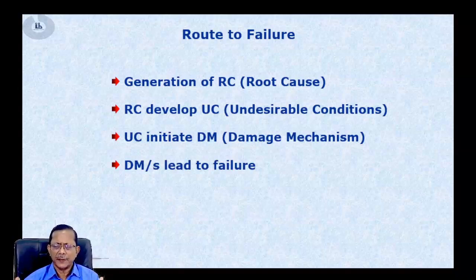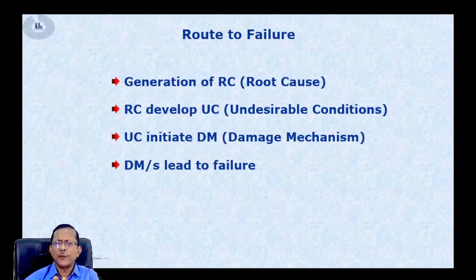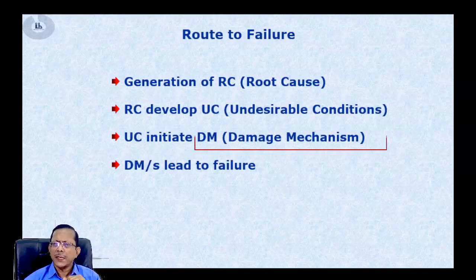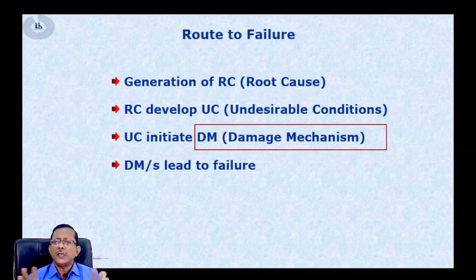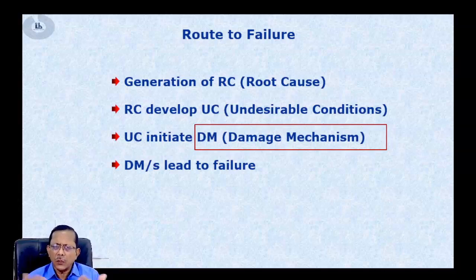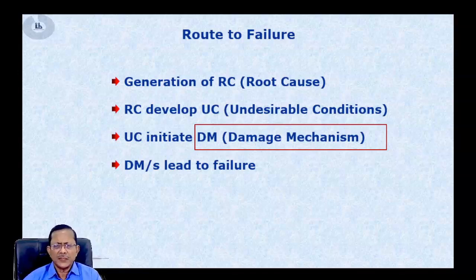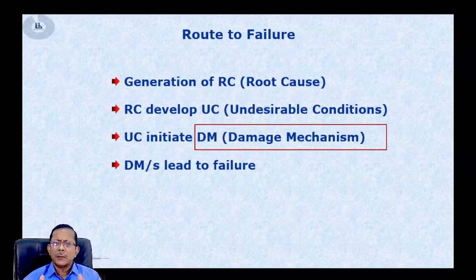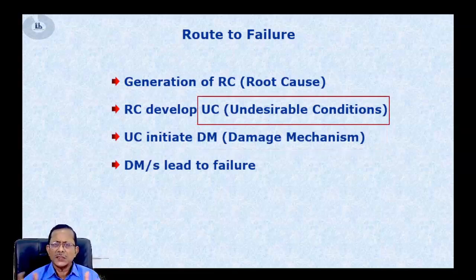Usually a damage mechanism takes time before it finally leads to failure. If I want to capture the problem before failure occurs, I can look for the damage mechanisms. For this I need to know what kind of damage mechanism is possible in a particular area. If I know that, I look for those damage mechanisms before a tube fails, replace the tube proactively, and actually prevent a tube failure.